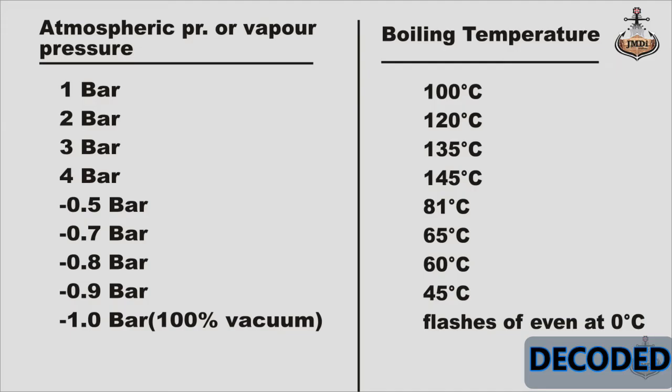Simultaneously, if you reduce the pressure or you create vacuum. So, at gauge pressure, minus 0.5 bar, the boiling point is 81 degree centigrade. At gauge pressure, minus 0.7 bar, boiling point is 65 degree centigrade. At gauge pressure, minus 0.8 bar, boiling point is 60 degree centigrade. At gauge pressure, minus 0.9 bar, boiling point is 45 degree centigrade. And at gauge pressure, minus 1 bar, that is 100 percent vacuum. Water flashes off at any temperature. But it should be above 0 degree centigrade, it should not be ice. Just flashes off.